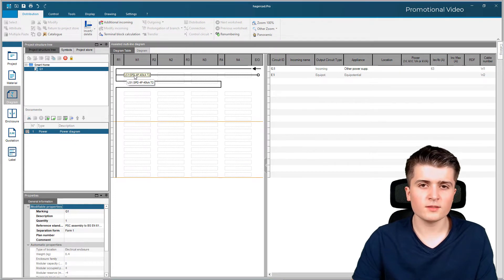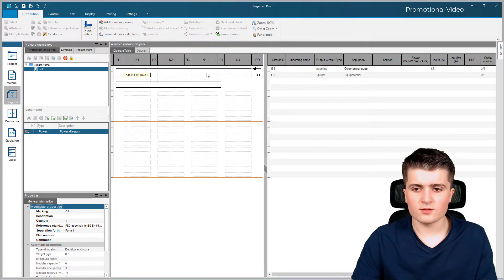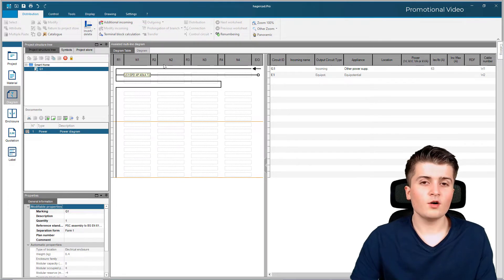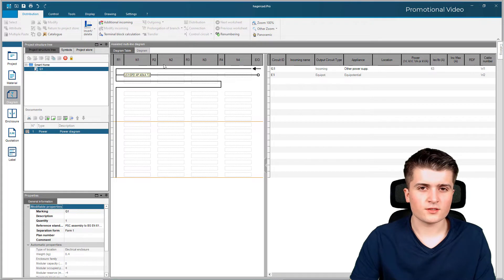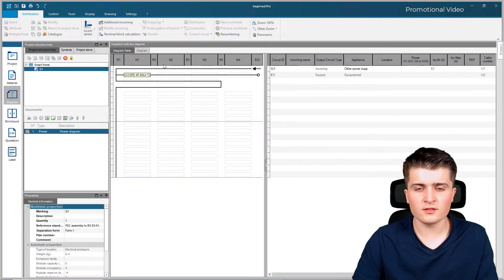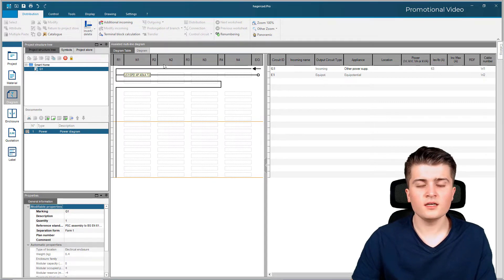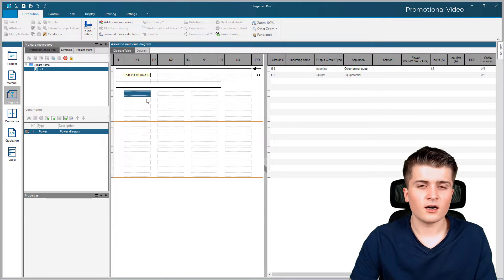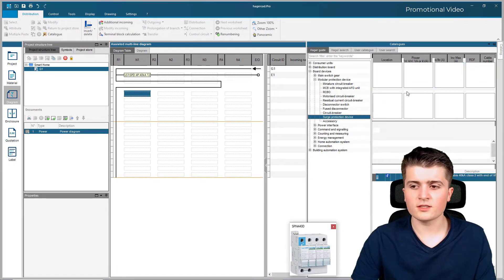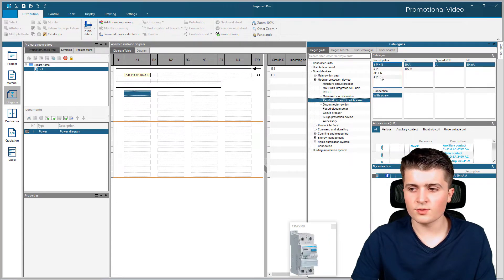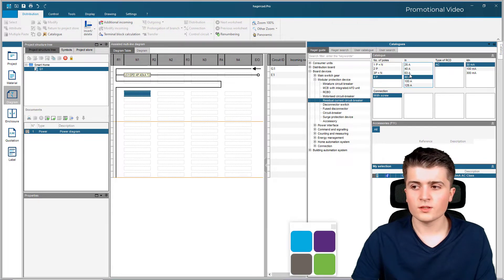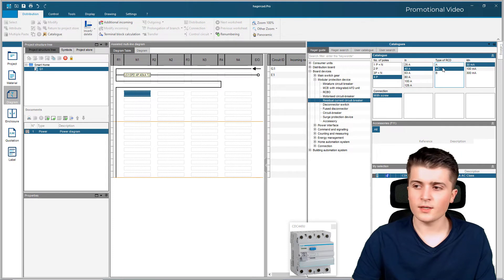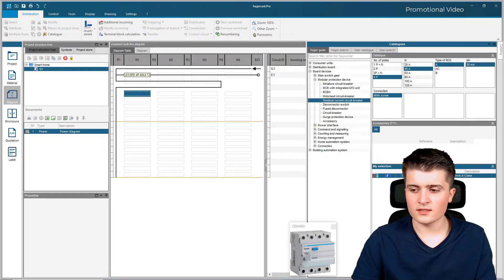This surge protective device type 2 only makes sense if in the incoming distribution we already have SPD type 1. We now have our surge protective device connected to our equal potential. Now we can start creating our first circuits. We wanted to add six lighting circuits secured by a combined RCD, with each circuit then secured by a circuit breaker. So I first want to add the RCD. I click on the first free field, go back to catalogs, and under residual current circuit breaker I specify four poles with 40 amps, type A, and 30 milliamps. Clicking add.